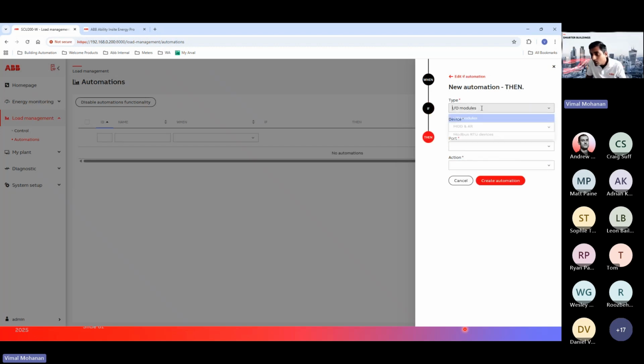Alternatively, you can connect what's called input-output modules that are available in the system. We've got 4-input 4-output, or 2-input 2-output modules. These modules, especially the output ones, can be connected to anything. You could connect it to a KNX switch actuator, so when that breaker exceeds X amount, that KNX switch actuator controlling lights could be turned off. If you just want a red light to come on to indicate something has gone wrong, you can do that.